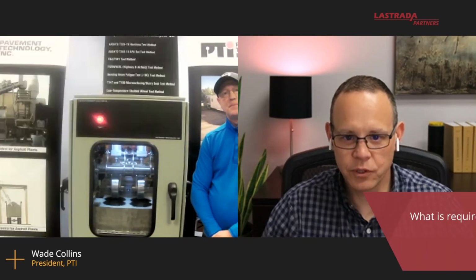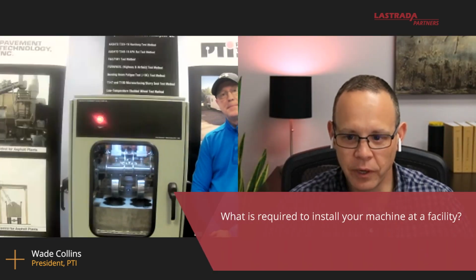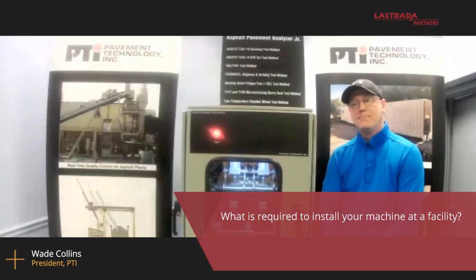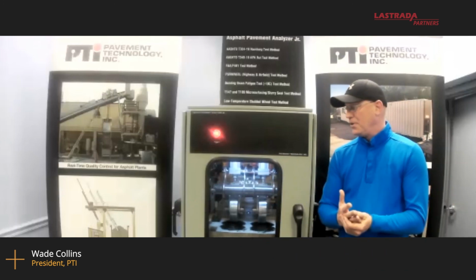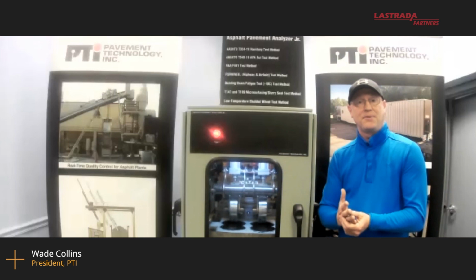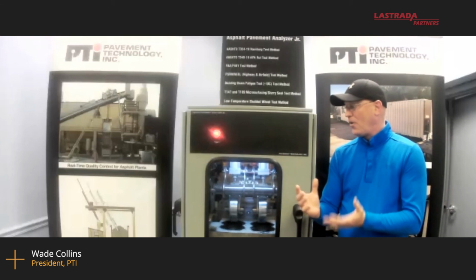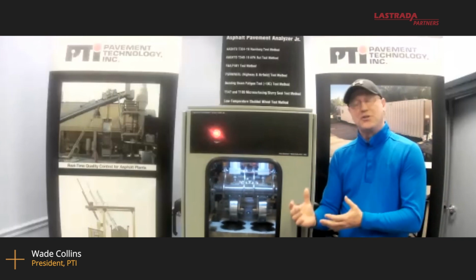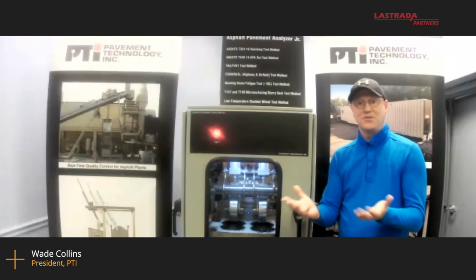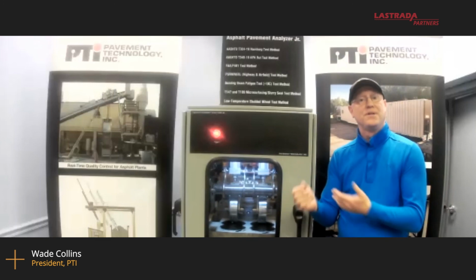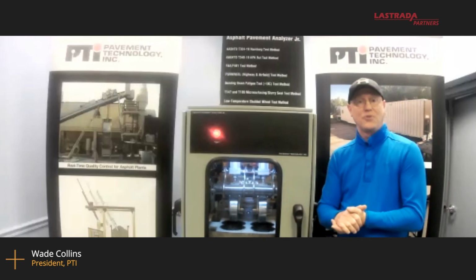So Wade, if somebody were to purchase an APA Junior, what would I need to do to prepare my building for that installation? The main thing you need is 230-volt electrical power, single phase, on a 50-amp breaker. That would take care of the electrical. You would need compressed air, 120 psi, in 3 to 5 standard cubic feet per minute volume to control the pneumatic system. And then you would either need to hard pipe in your water and drain, or if you want to bypass that, you could use a standard garden hose to fill the tank and to drain the tank as needed.